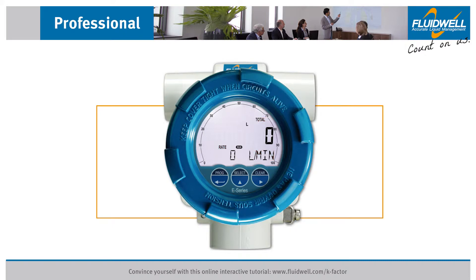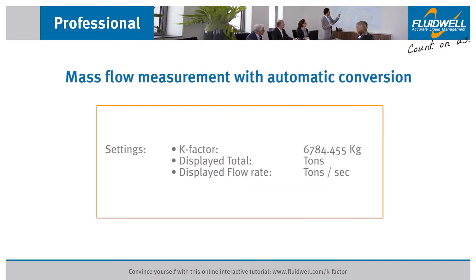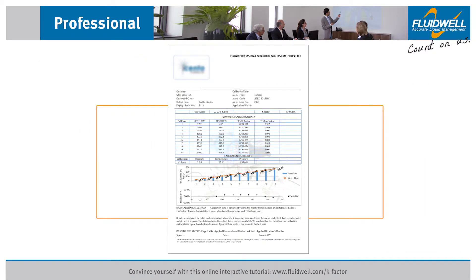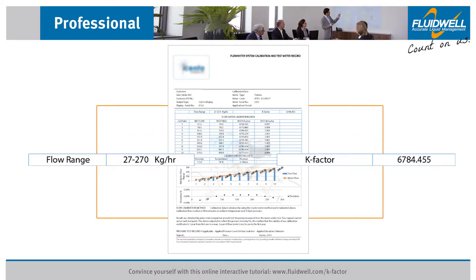The k-factor setting should be configured before installation to ensure correct measurements in any situation. In this tutorial we will set the k-factor for mass flow measurement with automatic conversion and configure the settings to display the mass total and flow rate. Before we set up the k-factor we need to identify this number as provided by the flow meter manufacturer. In this example, that is 6784.455 and the measurement unit is kilograms.